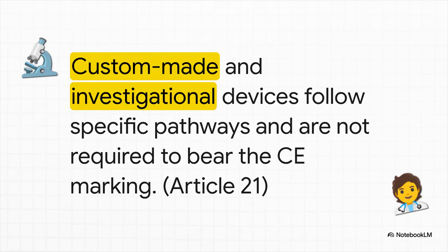The regulation is also smart enough to acknowledge some other unique cases. For instance, devices that are custom-made for one specific patient, or devices that are only being used for a clinical investigation. These follow different pathways. They don't need a CE mark, but they still have to meet other very strict requirements that are laid out in the regulation.